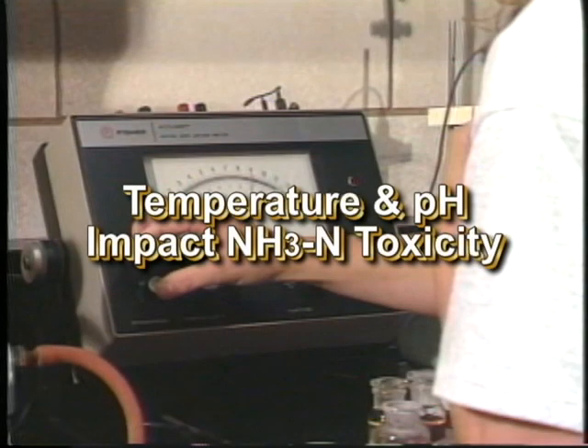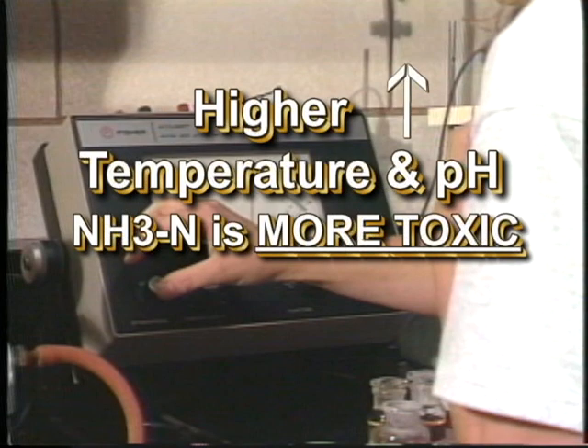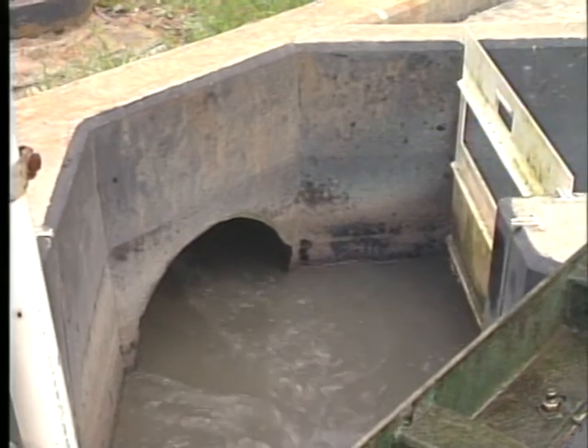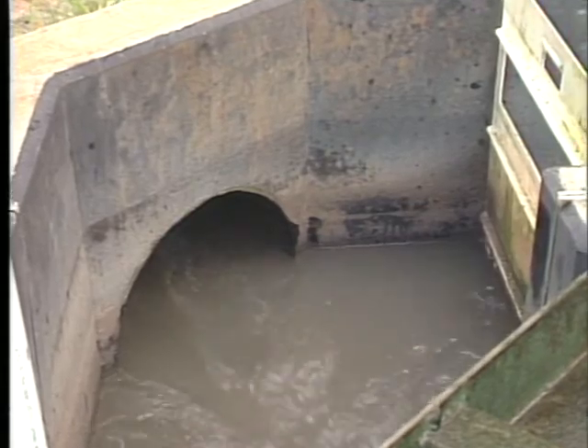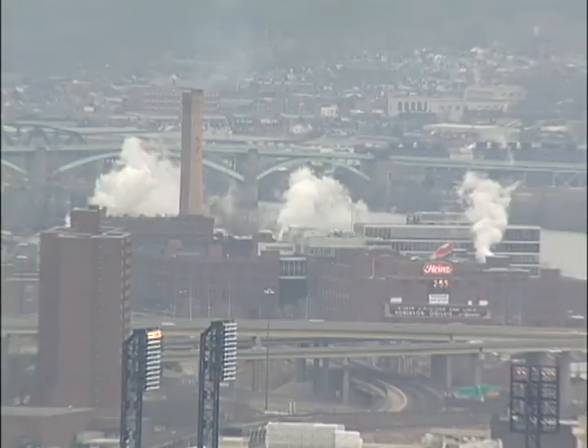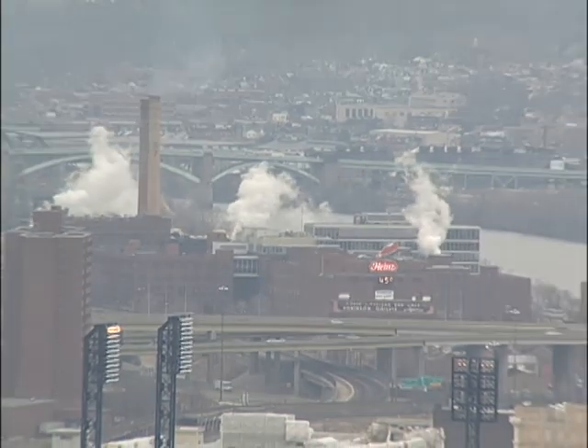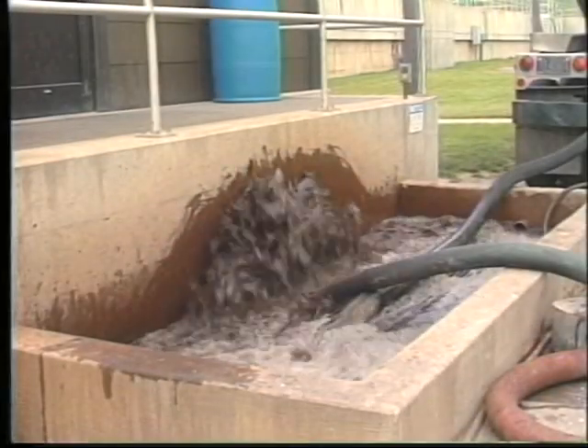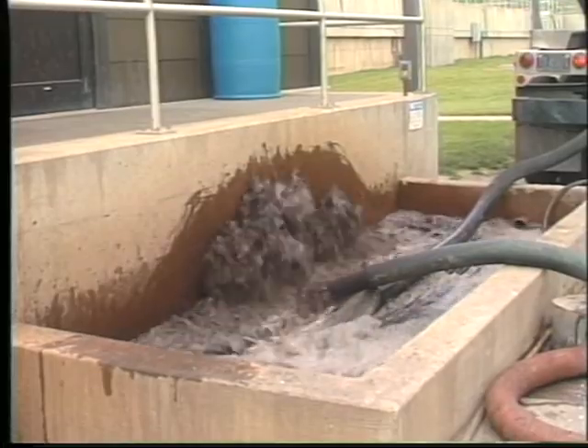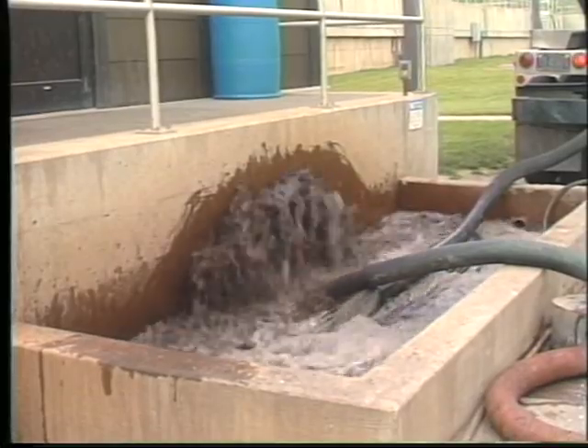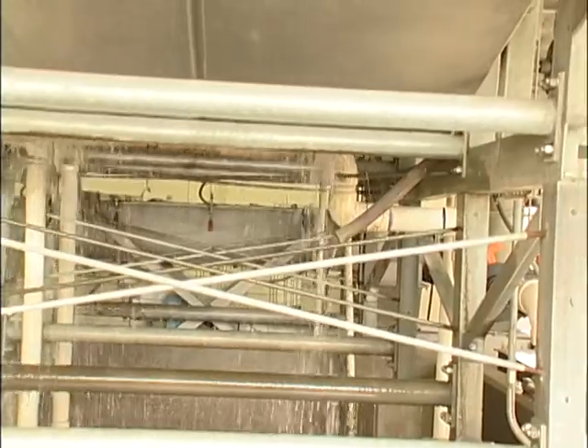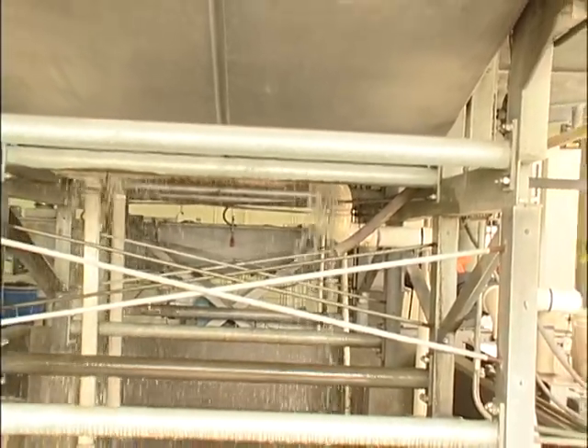The toxicity of ammonia is impacted by the water temperature and pH. Typically, the higher the temperature or pH, the higher the toxicity. Ammonia in wastewater can come from a variety of sources and is found in domestic wastewater. It also comes from non-domestic wastewater, such as industrial or institutional wastewater, trucked-in wastes, such as septage, and internal recycle flows, such as belt press filtrate or anaerobic digester supernatant.